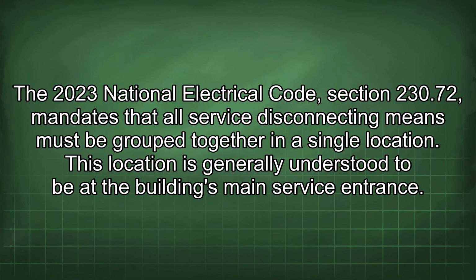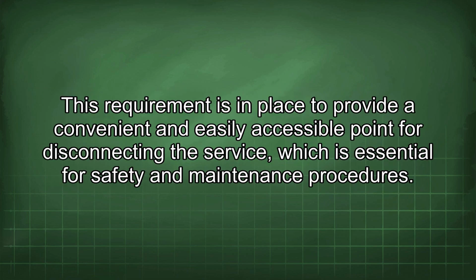2023 National Electrical Code, Section 230.72, mandates that all service disconnecting means must be grouped together in a single location. This location is generally understood to be at the building's main service entrance. This requirement is in place to provide a convenient and easily accessible point for disconnecting the service, which is essential for safety and maintenance procedures.